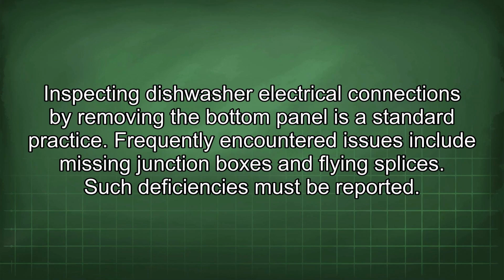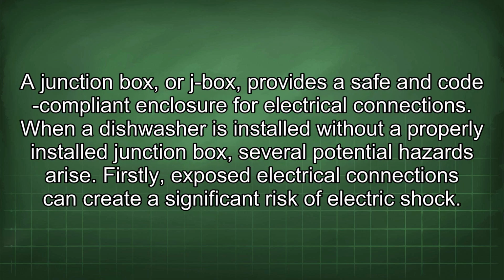Inspecting dishwasher electrical connections by removing the bottom panel is a standard practice. Frequently encountered issues include missing junction boxes and flying splices. Such deficiencies must be reported. A junction box, or J-box, provides a safe and code-compliant enclosure for electrical connections.